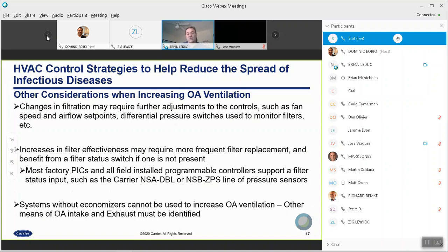If the filter switches are not there, and some of those are optional, you might want to propose to the customer that you add them, because again, more effective filtration will likely lead to a need to more frequently replace the filters, and the absence of a filter status will make it more difficult to know when that's required. So as Rich talked about the NSA and NSB sensors earlier, we do have a line of pressure switches that can be installed.